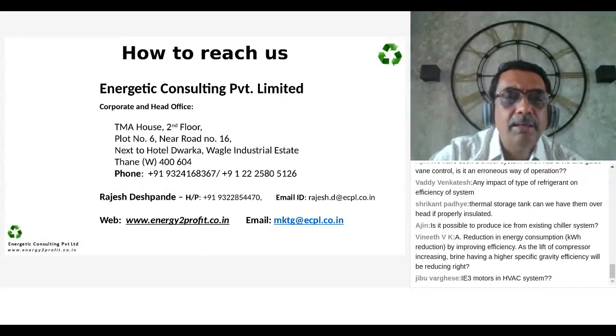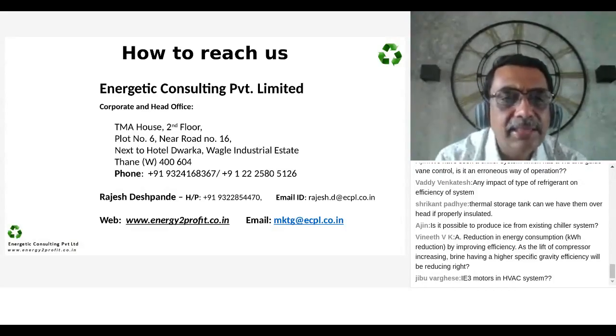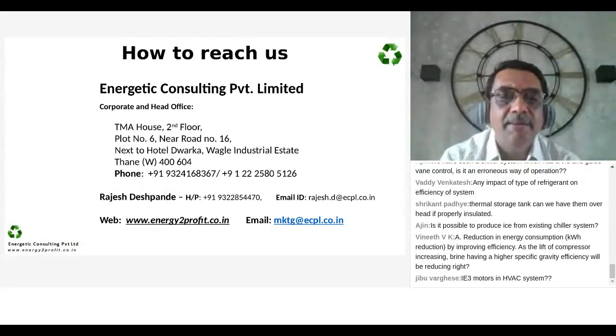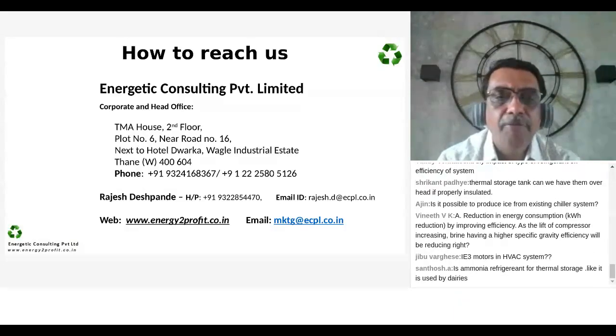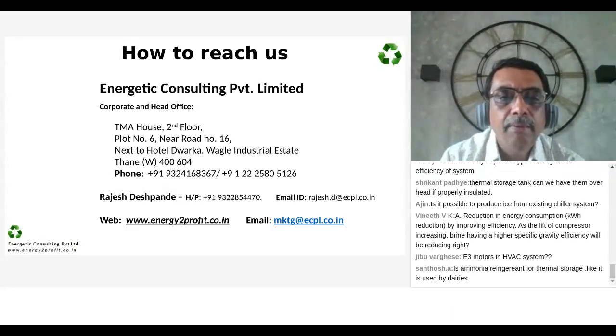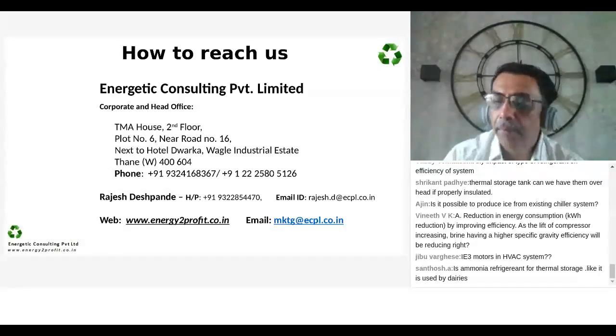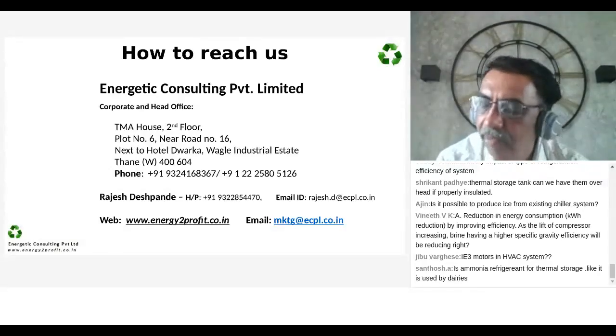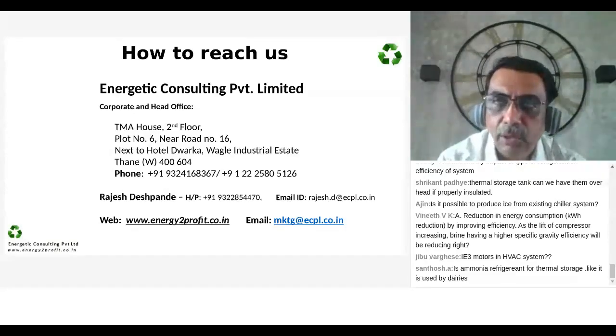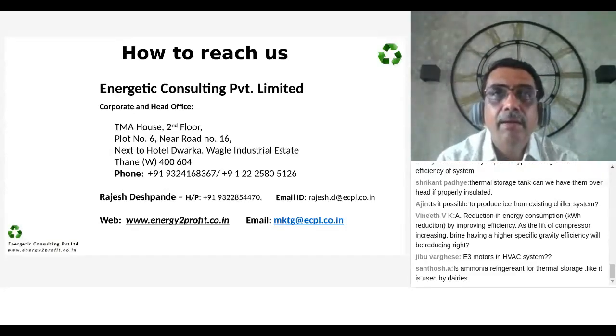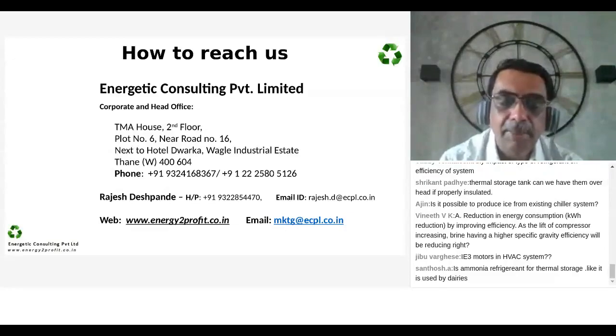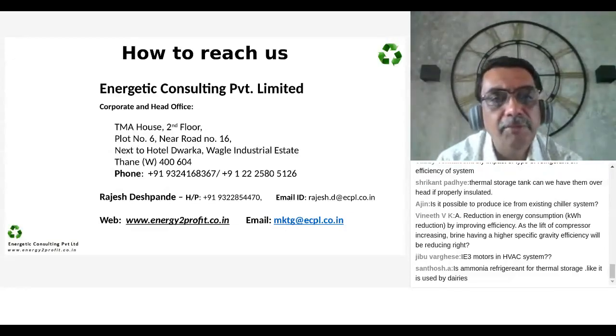The question is about reduction in energy consumption in kWh by improving efficiency. The question is very interesting: as the lift of the compressor increases, with brine having a higher specific gravity, will efficiency reduce? Not really. It is not a function of specific gravity. The efficiency is reduced because of the temperature lift. Brine is operated at -5, so the refrigerant is operated at -10. From 0 to -10, the refrigerant evaporating temperature goes down, and energy efficiency is reduced.